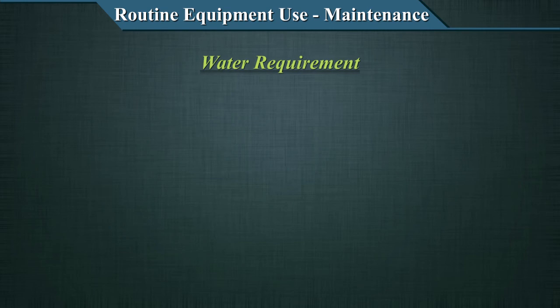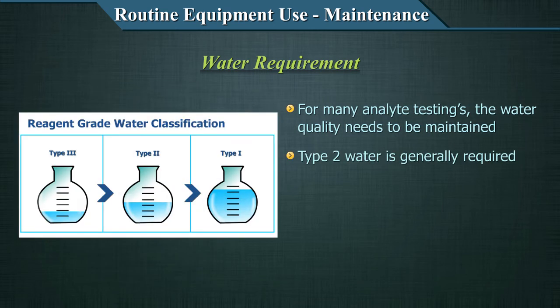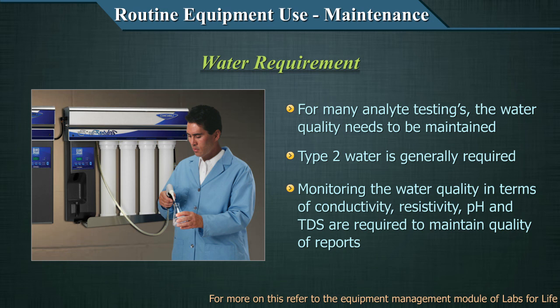Another important utility in the laboratory is water quality. Many analyte tests require water quality to be maintained — generally Type 2 water. Monitoring of water quality in terms of conductivity, resistivity, pH, and TDS (total dissolved solids) is required to maintain quality of reports for many biochemical analytes. For more on this, please refer to the equipment management module of Labs for Life.